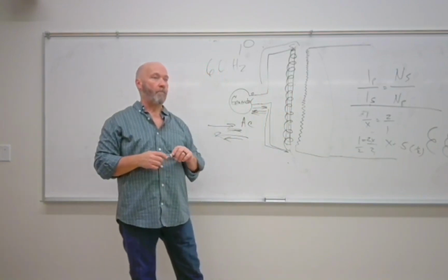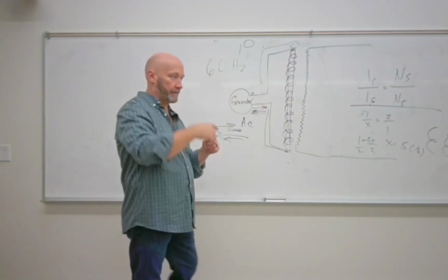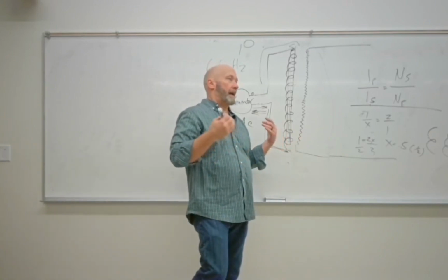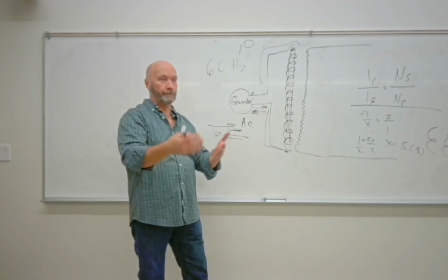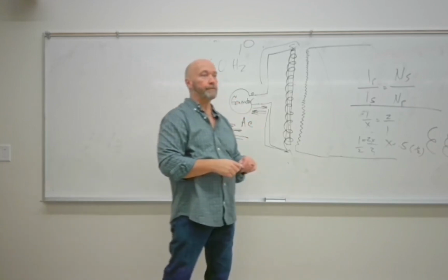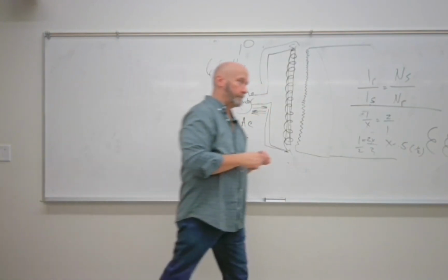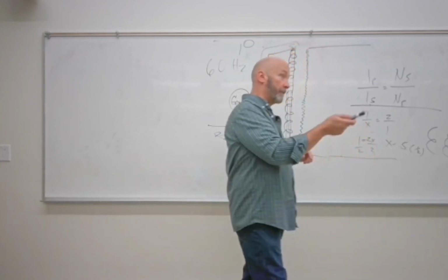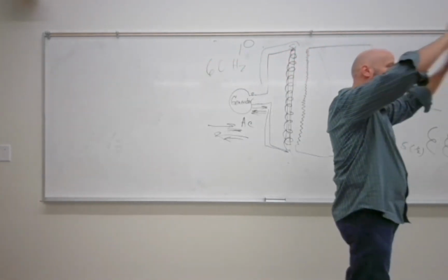So step down is always a factor of 2? Not necessarily. The filament current, the current that's going through the filament before we make an exposure, is about 25 volts. So if we had 250 volts going through our primary side, then it'd be a 10 to 1. I just use that for an example. Okay. So then the step up, you said it was direct, and the step down is inverse. Wait, no. Back up. In both cases, the voltage is direct. The amperage in both cases is inverse.